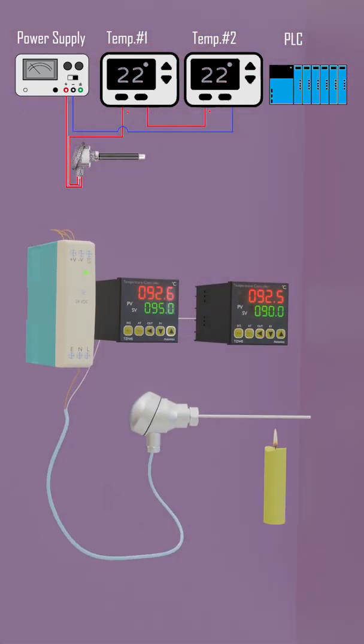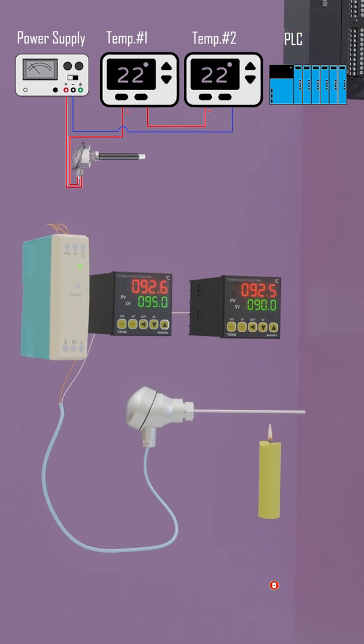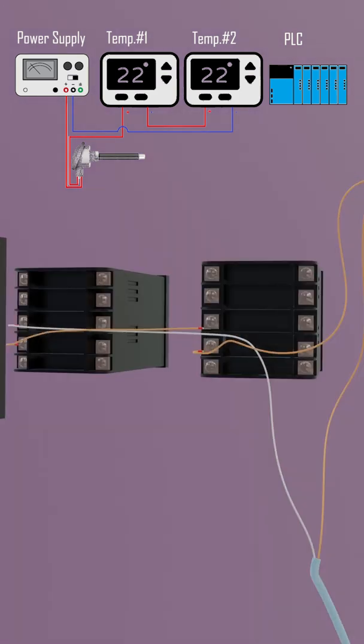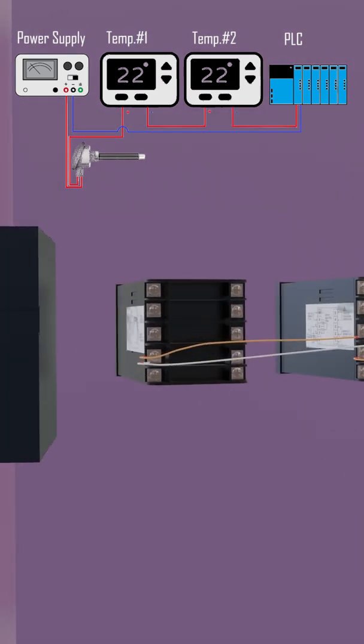Now the analog 4 to 20 milliampere signal from the temperature transmitter is traveling through both temperature controllers, and both are displaying the same temperature. We can even put a PLC analog input in series with this circuit and this PLC can now also read the analog signal from the temperature transmitter.